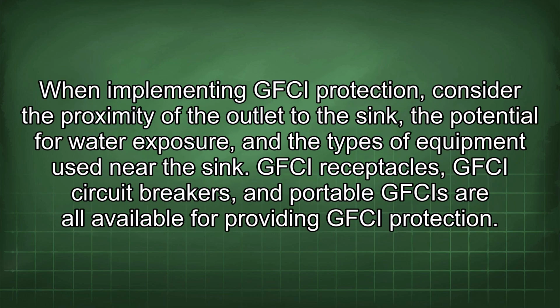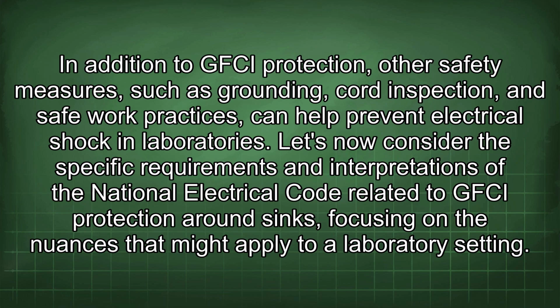When implementing GFCI protection, consider the proximity of the outlet to the sink, the potential for water exposure, and the types of equipment used near the sink. GFCI receptacles, GFCI circuit breakers, and portable GFCIs are all available for providing GFCI protection. In addition to GFCI protection, other safety measures such as grounding, cord inspection, and safe work practices can help prevent electrical shock in laboratories. Let's now consider the specific requirements and interpretations of the National Electrical Code related to GFCI protection around sinks, focusing on the nuances that might apply to a laboratory setting.